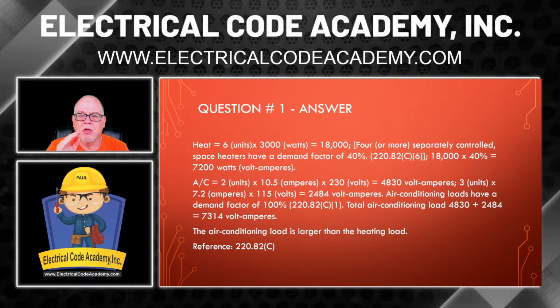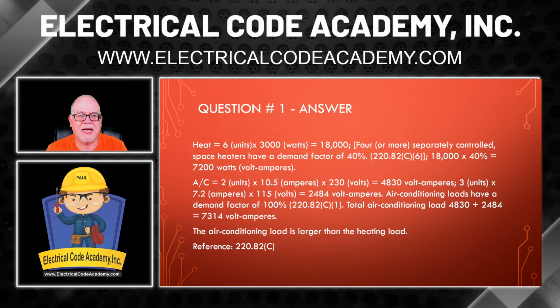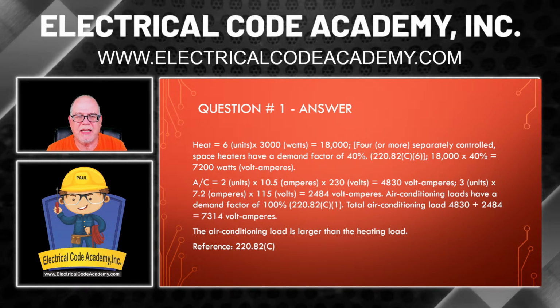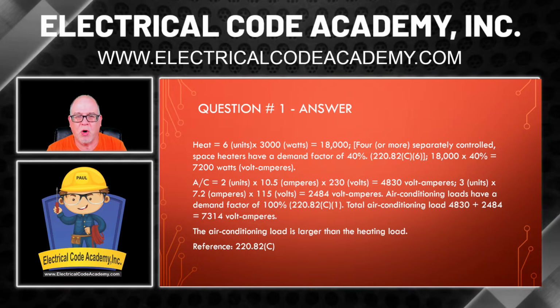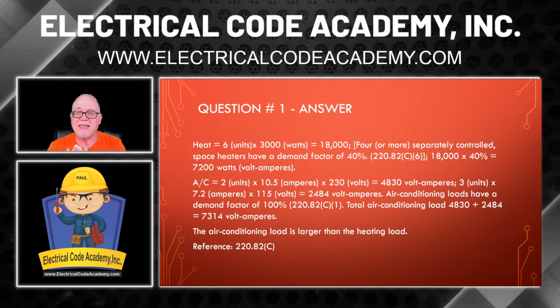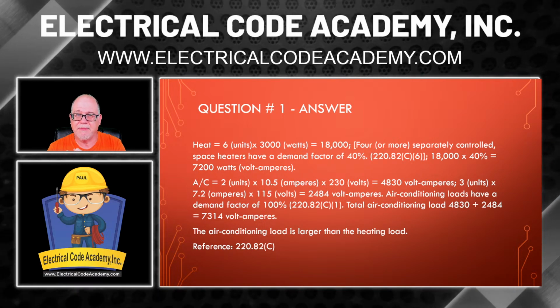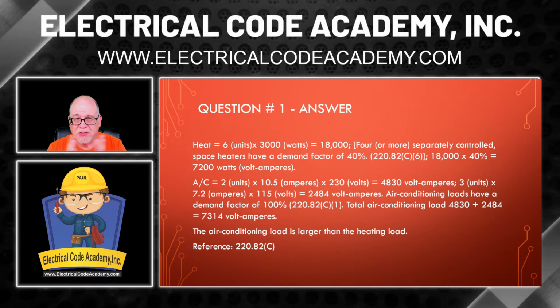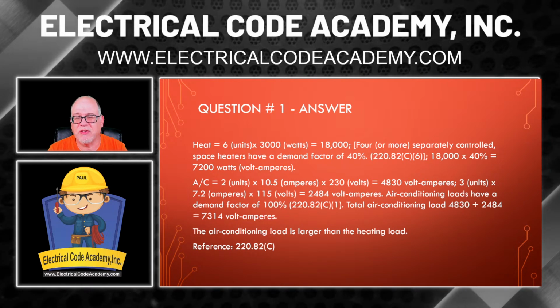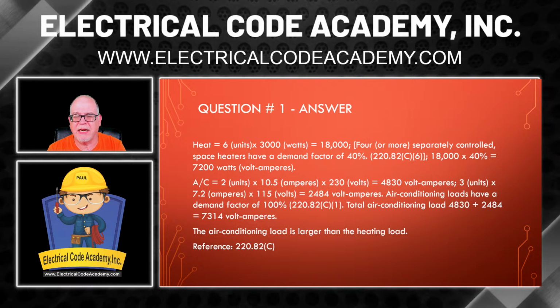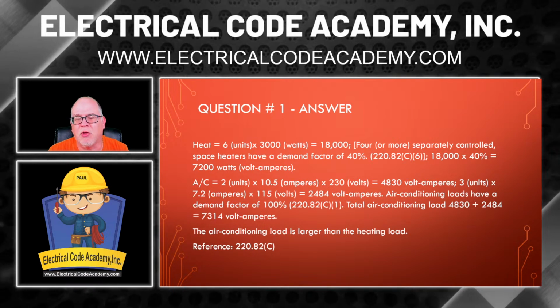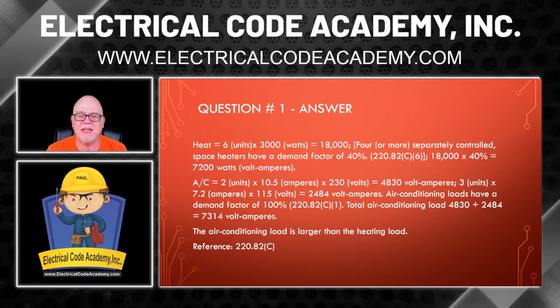All right. So now we want to do 3 times 7.2 times 115. That's 2,484 VA. So all we're going to do is remember, we take them at 100%, right? So we're going to add the 2 together. So 4,830 plus the 2,484, add them together. That's 7,314 VA.